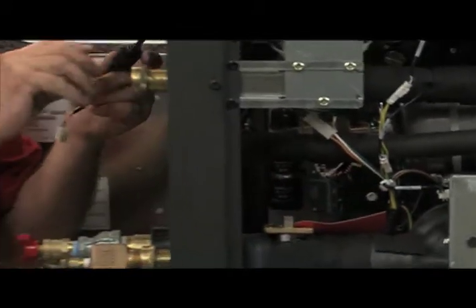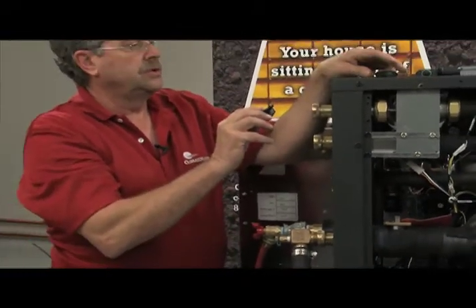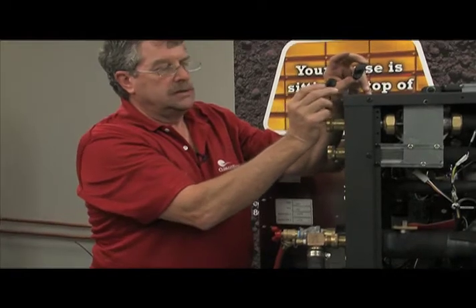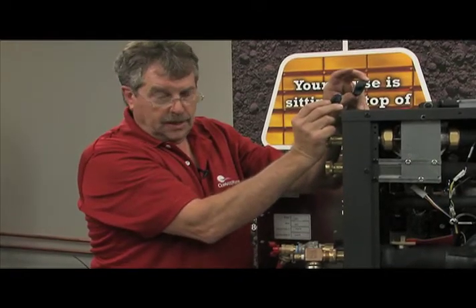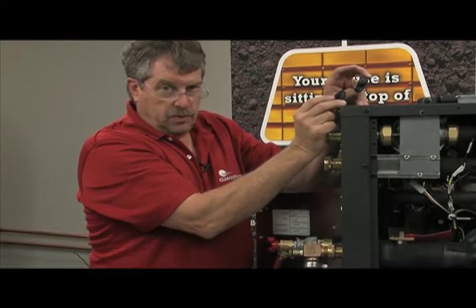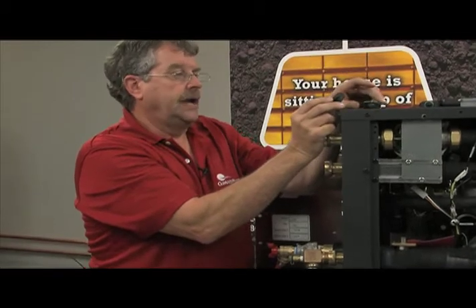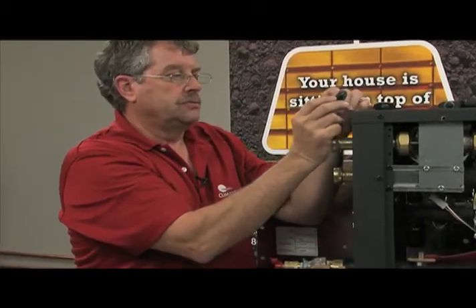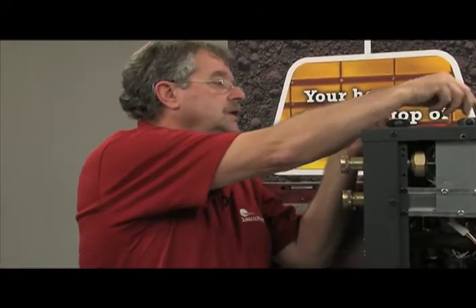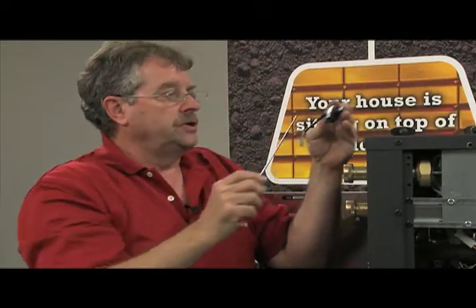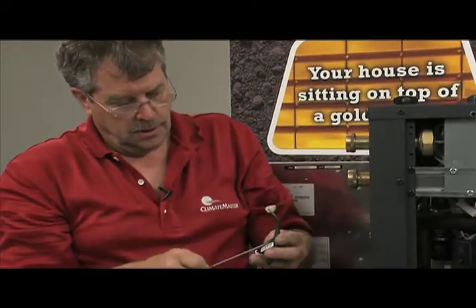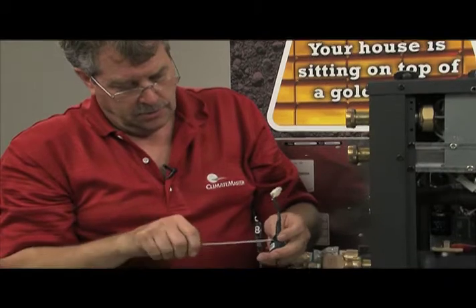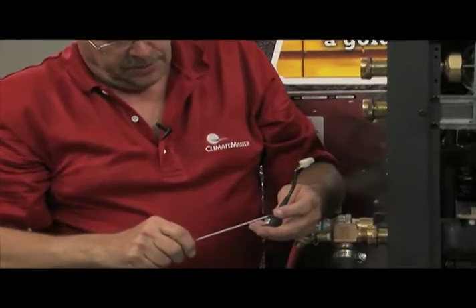I know it's the old sensor. Now one of the things you'll probably find is that rubber boot I showed you earlier in the video remained inside the fitting. Usually it's best to remove that rubber boot and go with the new one on the new sensor. But one thing you're also going to need to do is remove the Grundfos connector. It's got a little bit of a retaining clip.